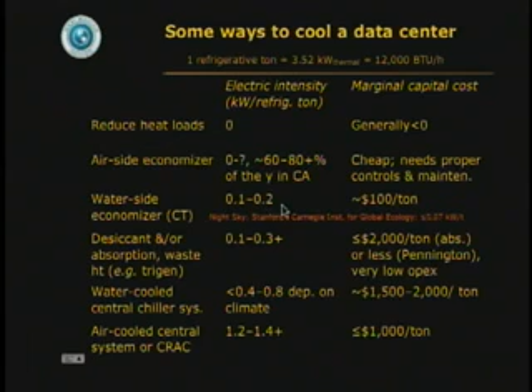But go down the street to Stanford's Carnegie Institute for Global Ecology. They have a small server farm in there, a closet stuffed full of servers, and that uses the night sky passive cooling system, radiant heat going away from water trickled down the roof, and that gives 0.07 or better kilowatts per ton, even better than this waterside economizer because it gets more radiative cooling. Compare that with 1.2 to 1.4 kilowatts per ton, and you can see what a good deal it is.